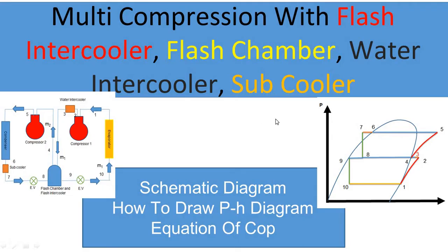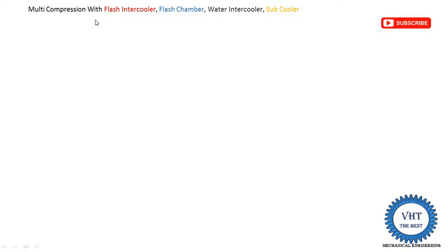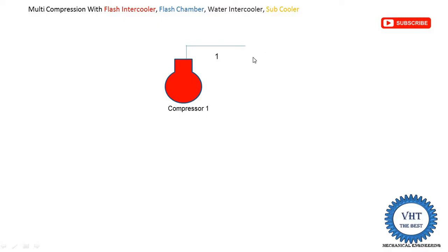This system is multi-compression with flash intercooler, flash chamber, water intercooler, and subcooler. Multi-compression means it has two compressors, one flash intercooler, flash chamber, water intercooler and subcooler, then one condenser and only one evaporator. We start from the low pressure compressor, that is compressor one. The vapor refrigerant at low pressure coming out from the evaporator is supplied into this compressor at point number one, and the outlet point is point number two. So one to two is an isentropic compression process — isentropic means constant entropy.